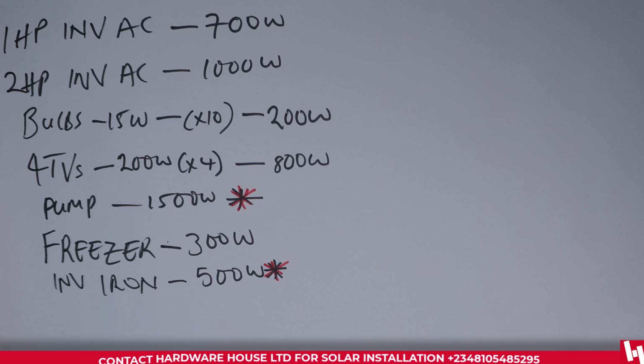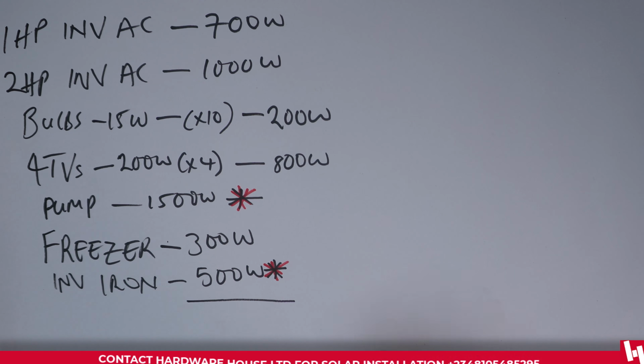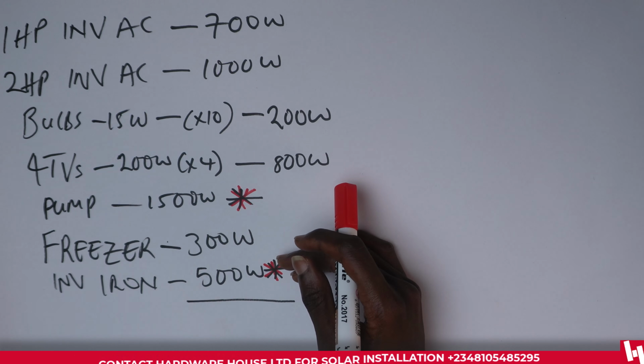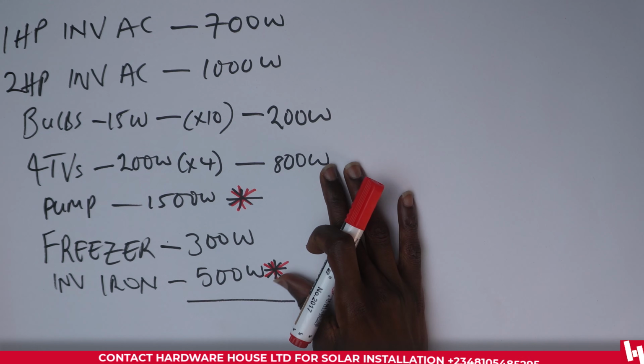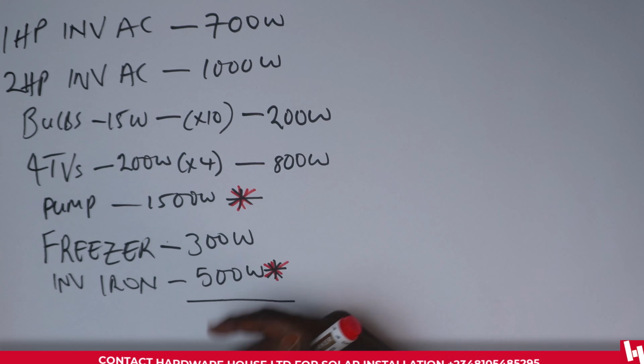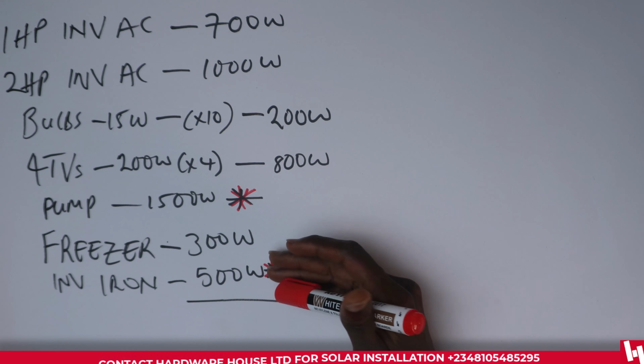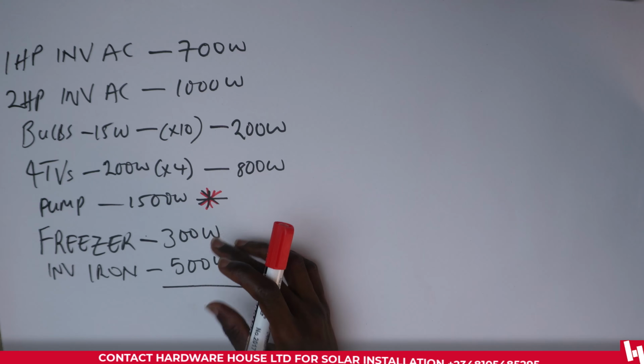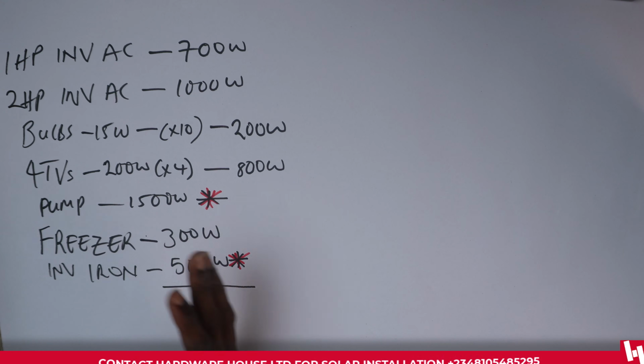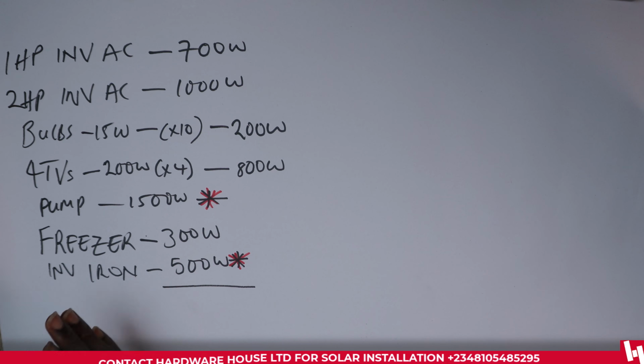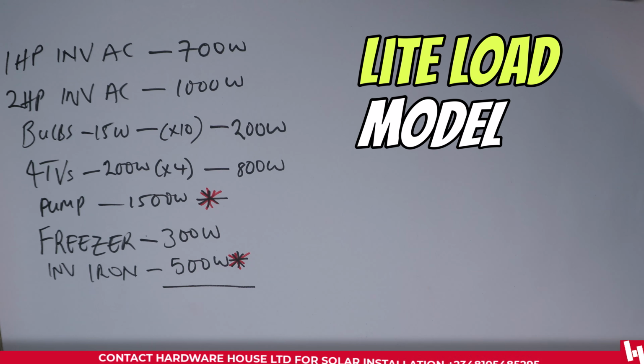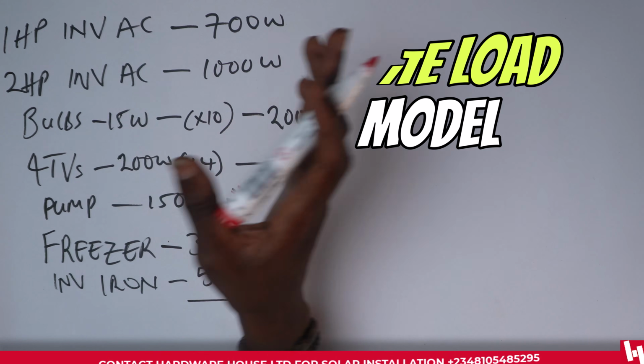So let's get the total. What I'm going to do is split this system into 2. One for nominal load, and that would exclude the pumping machine and the inverter iron. And then we would have the maximum possible load, which is everything here, including the iron and the TVs. That's when they are all running at the same time. Although our client told us that he doesn't want to be running all this at the same time, he wanted a very light system. That's why we called it a light load model. But in order to give him the maximum possible allowance, we calculated everything to be running together.